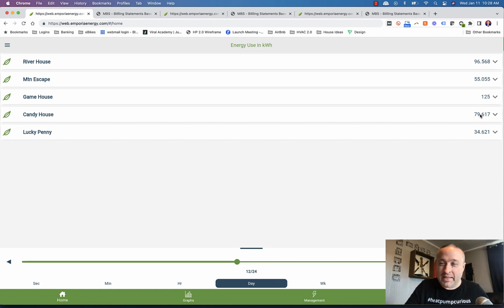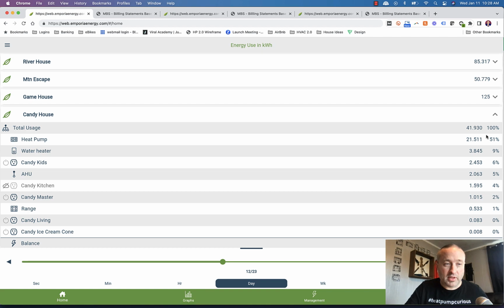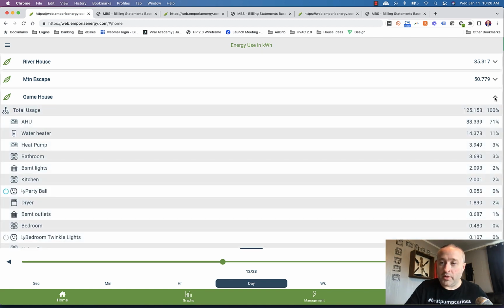So the Candy House used 79 kilowatt hours this day. The day before, it's going to be quite a bit less - let's go to the 23rd. The Candy House only used 41 this day, and the heat pump used 21. Where the Game House, the heat pump only used 4 because it got cold and shut off the heat pump. And so it ran a ton of resistance, see 88 kilowatt hours of resistance. So that's what happened that day with it.